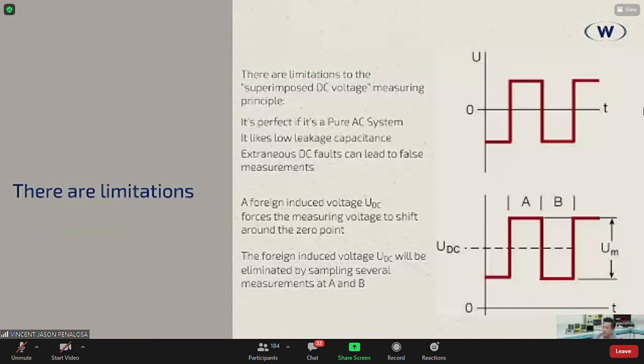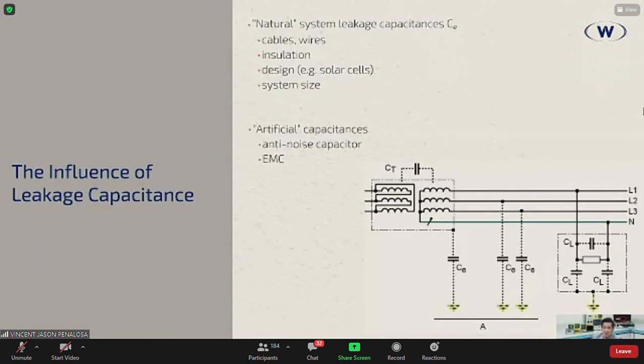Now, since we're at the topic of leakage capacitance anyway, how does it influence your measuring? First, you have natural system leakage capacitance. And this comes from your cables, your wires. We know for a fact that there is no perfect insulation. You have your design. So for the photovoltaic, maybe you have wind, you have whatever. And then the system size. The bigger the system, the higher the leakage capacitance. And then you have the artificial capacitances. When we talk about the anti-noise capacitor, this could be either a passive harmonic filter or an active harmonic filter, or it can be an electromagnetic, an EMC filter. Either way, it is artificial capacitances. Okay?